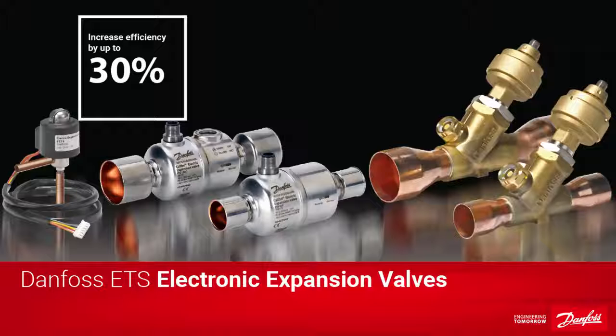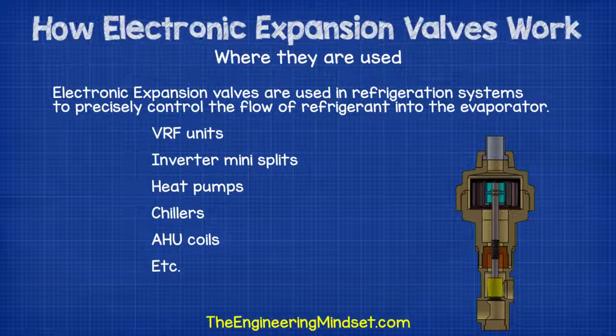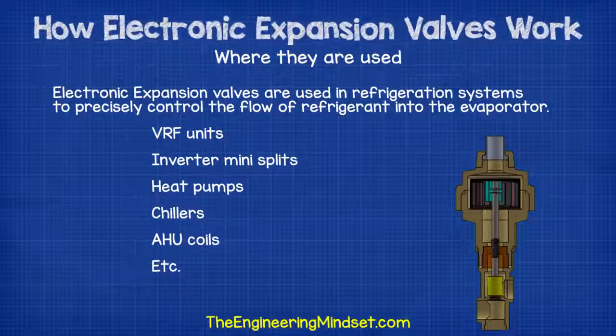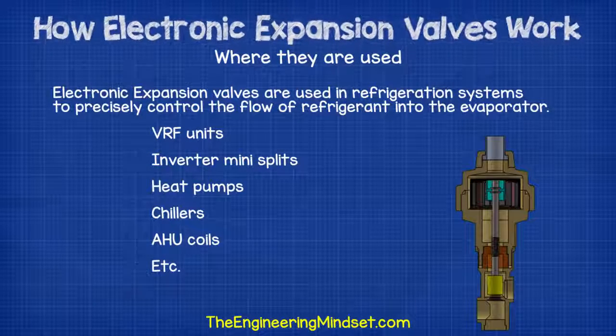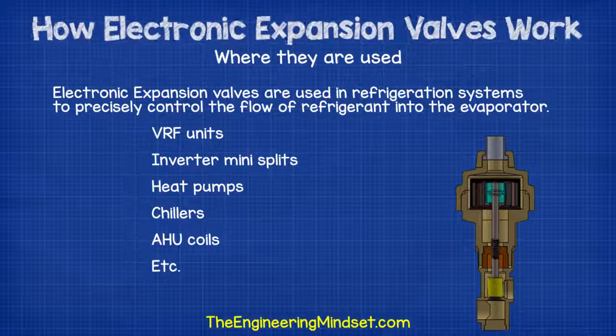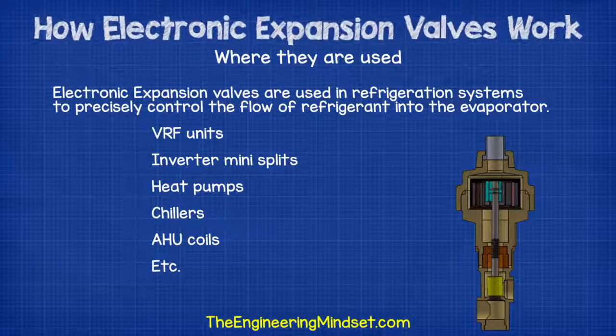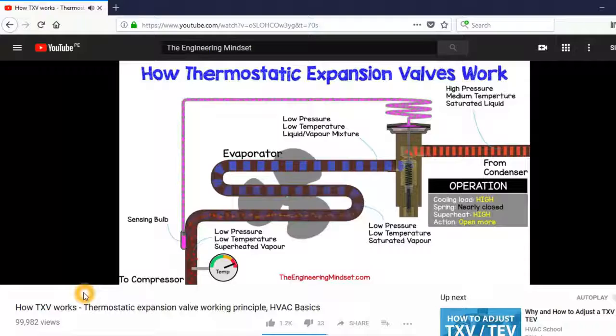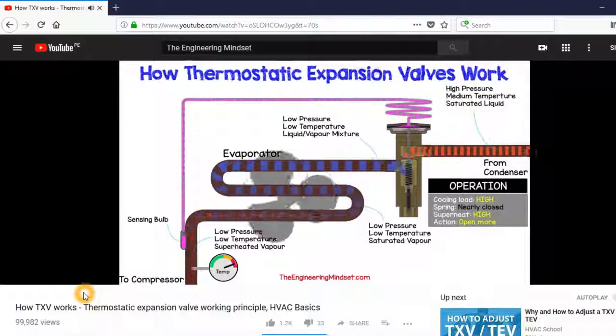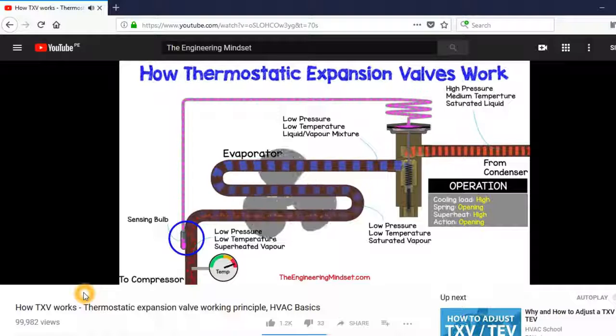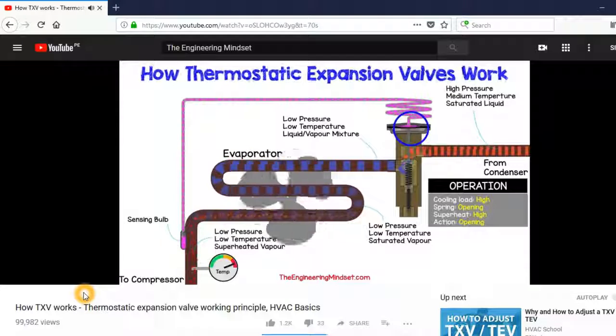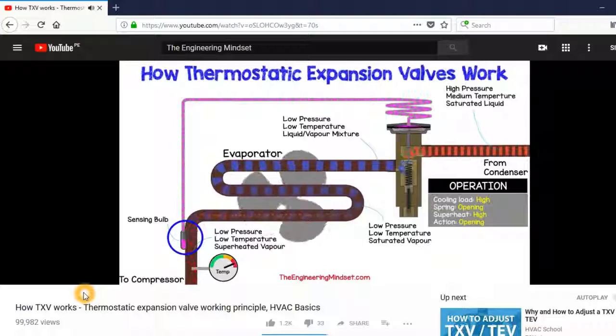Electronic expansion valves are used in refrigeration systems to precisely control the flow of refrigerant into the evaporator. You can find these on everything including VRF units, inverter mini splits, heat pumps, chillers, AHU coils, etc. Now, we've previously covered how thermal expansion valves work. These are very common in refrigeration systems, but they are nowhere near as efficient or precise as an electronic expansion valve. If you haven't watched the video on how these work, then I highly recommend you do so. Links are in the video description below.